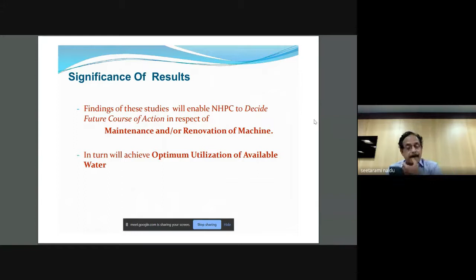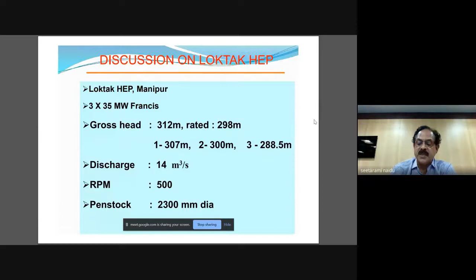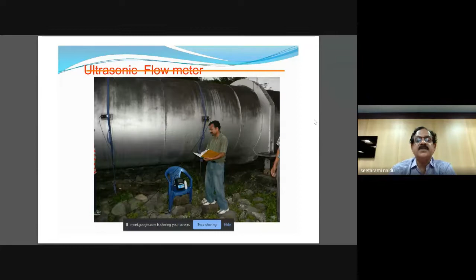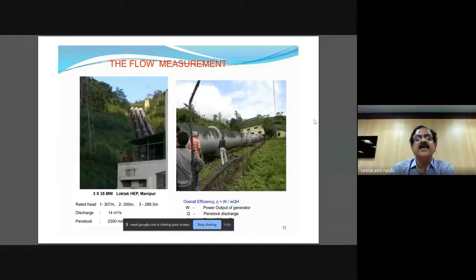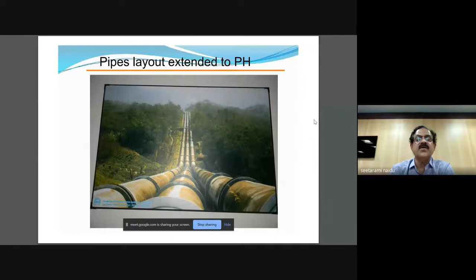The test we have done for the Loktak hydroelectric power plant: there were 3 turbines of 35 megawatt each. The head was around 300 meters, and the discharge contemplated was 14 meter cube per second. RPM of the runner was 500, penstock diameter 2.3 meters. This is how we utilized an ultrasonic flow meter in the penstock, somewhere in a horizontal stretch. It had sufficient upstream and downstream length. This is the situation in the bird's eye view: the penstock going through hill terrain. This is the turbine.